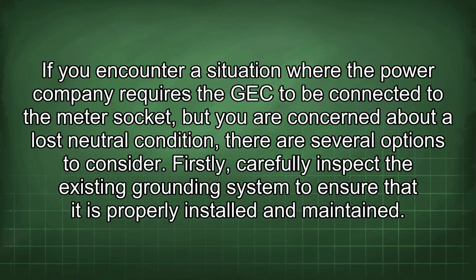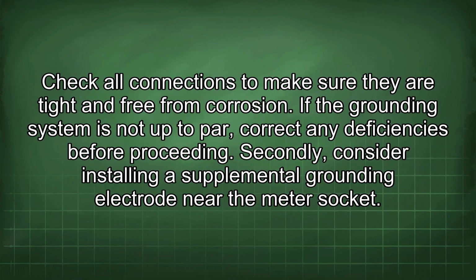If you encounter a situation where the power company requires the GEC to be connected to the meter socket but you are concerned about a lost neutral condition, there are several options to consider. Firstly, carefully inspect the existing grounding system to ensure that it is properly installed and maintained. Check all connections to make sure they are tight and free from corrosion. If the grounding system is not up to par, correct any deficiencies before proceeding.